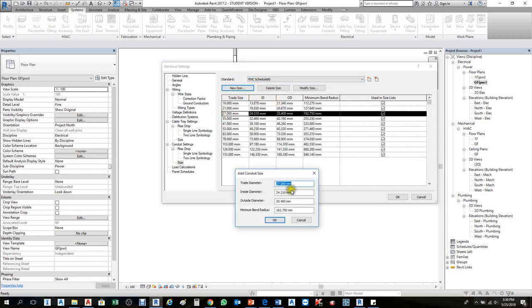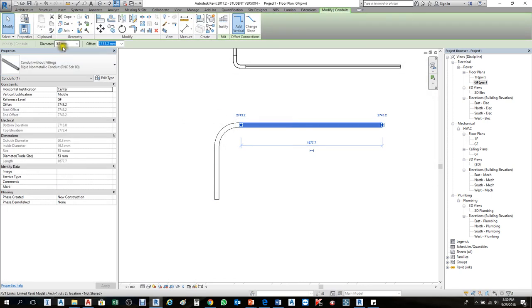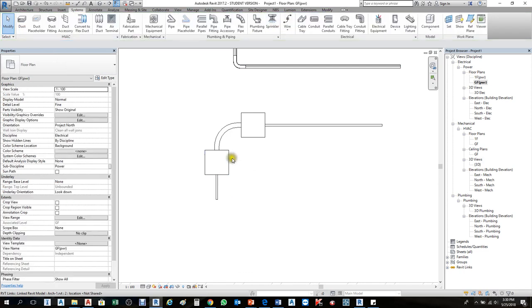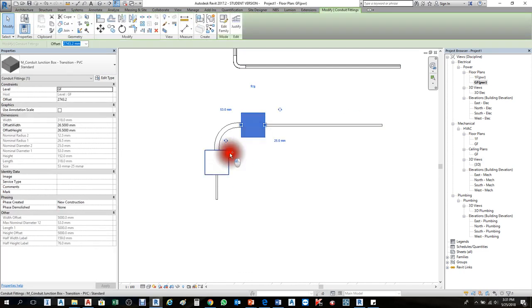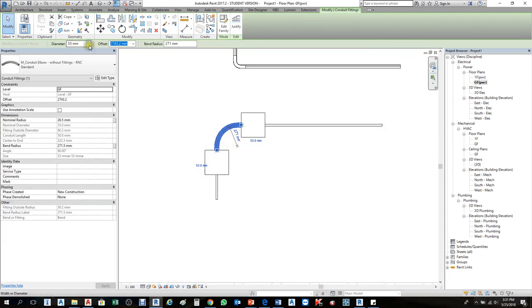Under RNC type, go to conduit size, choose RNC 80 — we have 27 there. I'll add a new size: 25mm, set the thread diameter, inside diameter, and outside diameter to 25. The minimum radius is the bending limit — by default it gives 162mm. When you bend the conduit from horizontal to vertical, this is the minimum. If you need 90 or 45 degrees and the limit is 162, you cannot exceed it. I'll press OK and now 25 appears in the conduit size list.